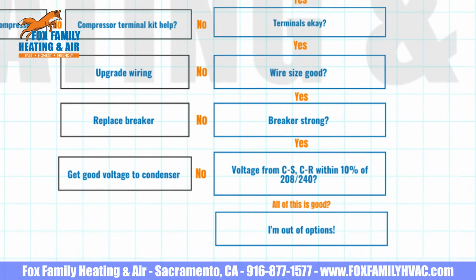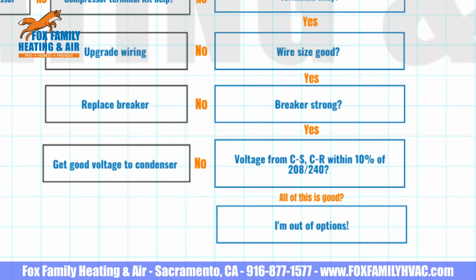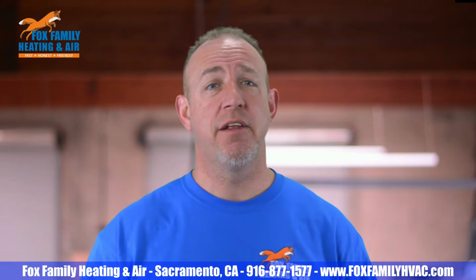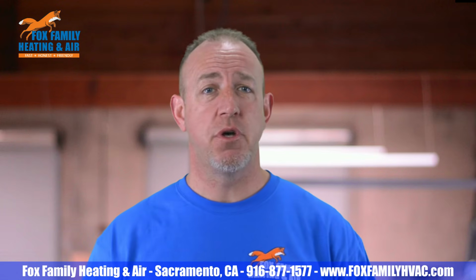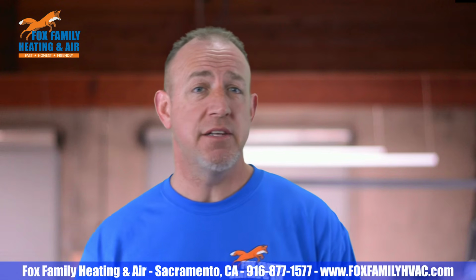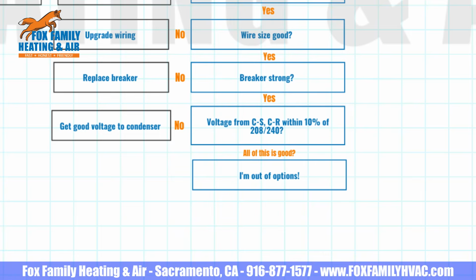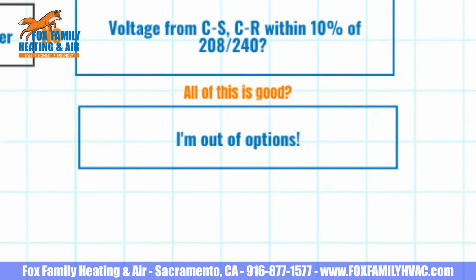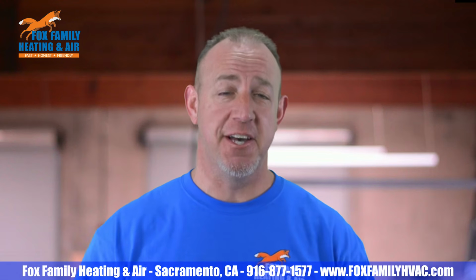One final check that you could do is upon startup, you can check the voltage from common to start and common to run. It'll probably take 2 different meters so you can check it simultaneously, but the voltage needs to be within about 10% plus or minus of its rated voltage. Residential motors are rated for 208 to 230 volts, so verify the voltage is above 187 and no higher than 253 volts. If running through this chart doesn't find your problem, then I don't know what to tell you.